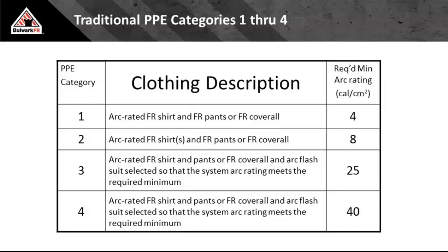So remember back to 8 and 3. What's the advantage of doing the incident energy analysis method versus the Cat method? The advantage is when you get up over Cat 2 or up over 8 calories. Look at the difference between 8 and 25. Now, I'm not a super math major, but that's 17 calories of separation between 8 and 25.